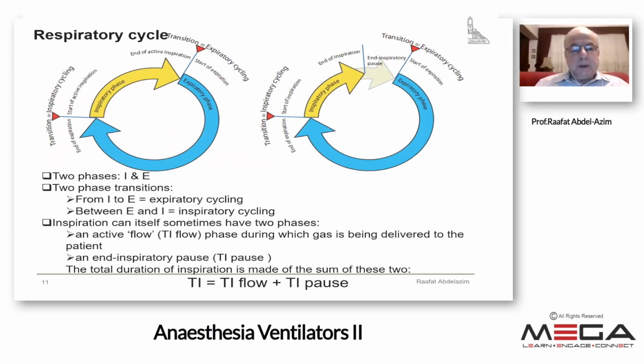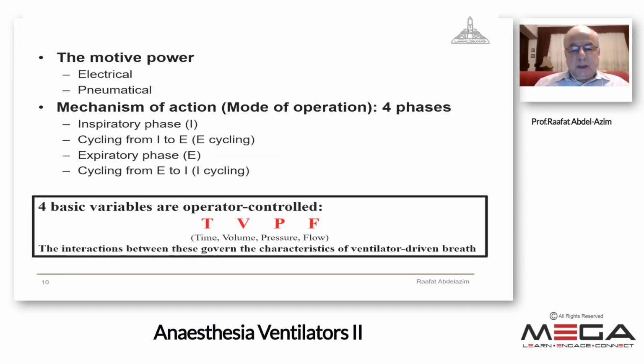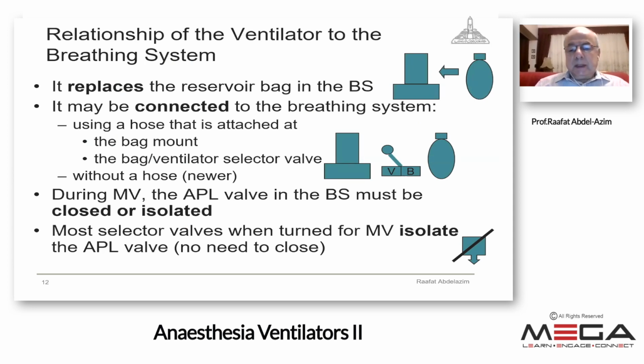This is a respiratory cycle, which consists of inspiration and expiration, and there should be a cycling from inspiration to expiration and cycling from expiration to inspiration. And this cycling depends on achieving either tidal volume or time or pressure or flow, as I will say later. To start mechanical ventilation, we have to push the button of start or have it in the on condition. When we switch to on, we have to connect the ventilator by a hose or switch, bag/ventilator switch, or lever or selector. And in newer versions of ventilators, these two steps of connecting a hose or selecting a ventilator are shortened and there is no need to do this.